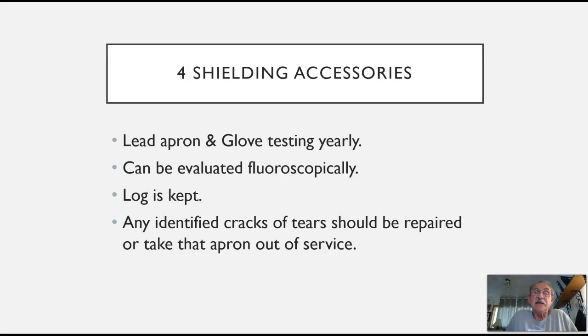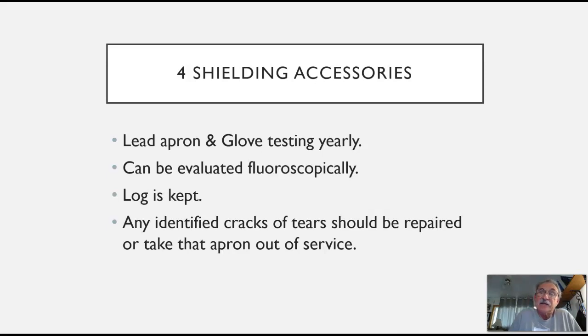We also have shielding accessories — lead apron and glove testing, done on a yearly basis. Typically that can be done fluoroscopically as opposed to taking X-ray images. We keep a log of our shielding accessories and whether or not they have any cracks or splits in them. Any identified as having cracks or tears should be repaired, or we take that apron out of service. Remember, they have lead in them, so they need to be disposed of as hazardous waste.